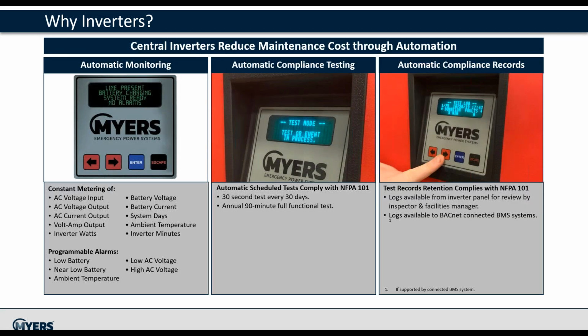One of the greatest assets of the inverter system is the simple diagnostics offered: monitoring, testing, and historical records in the form of alarm and test logs. The NFPA compliant automatic testing and logging feature stores the results from 2 years of monthly and yearly tests internally in a non-volatile memory, easily viewed by the local inspector. This data can also be made available via communication systems such as BACnet to the BMS system.